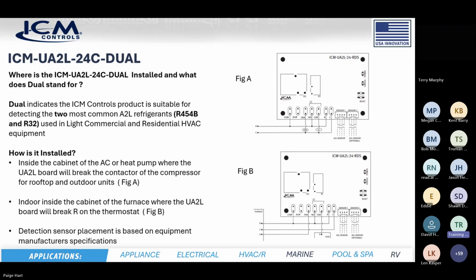So again, we make this for the OEM, but we also now are offering this as the dual for the aftermarket. So how's it installed? Well, you can install it inside the cabinet of your AC or heat pump, where the UA2L board will break, let's say, the contactor of a compressor in your AC unit, or in a heat pump, it'll also break the compressor contactor. This basically shuts off the system, right? And it'll turn on the fan. And then for rooftop units, same thing.